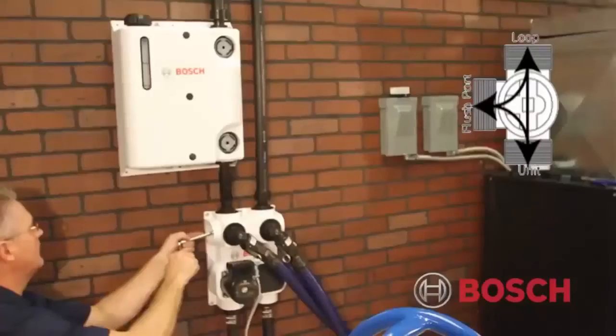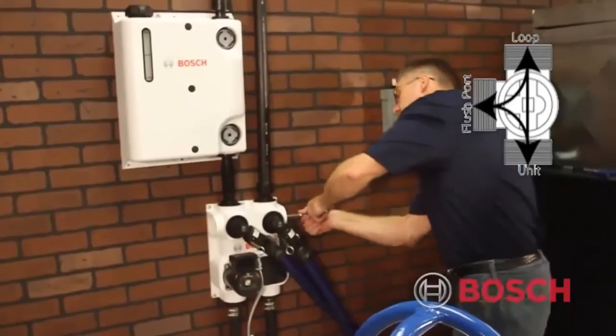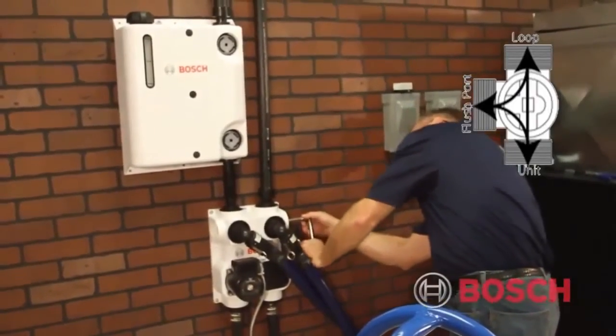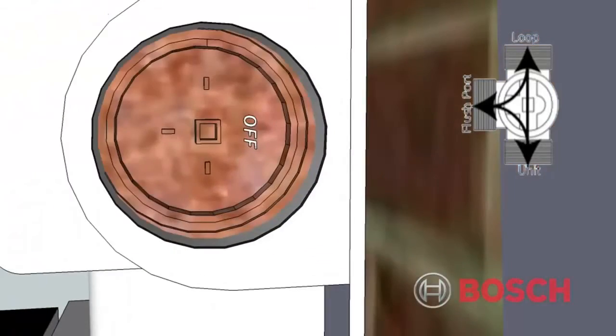Starting with the flow center return three-way valve, rotate the off mark to the full flush position, following immediately with the discharge three-way valve. In this position, the flush cart purges the air from the unit and the ground loop at the same time. It's recommended to purge the system in full flush position for a minimum of 2 hours.